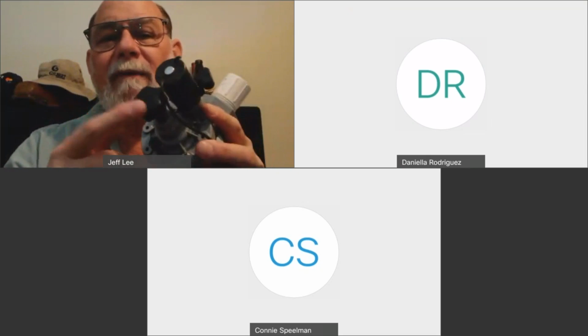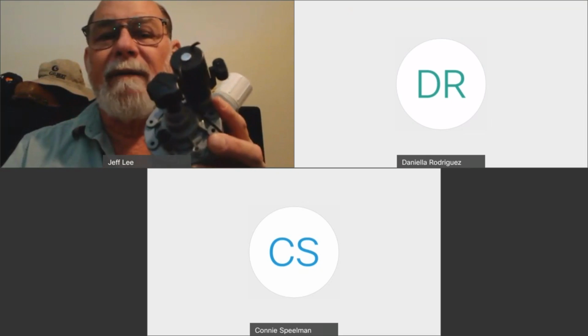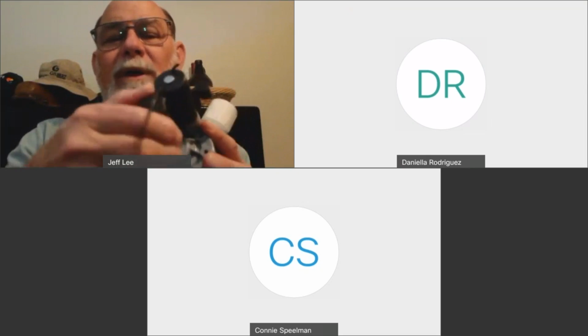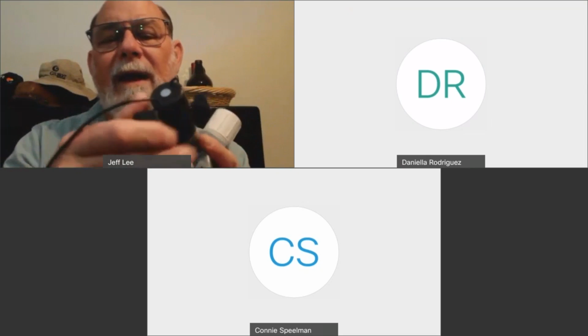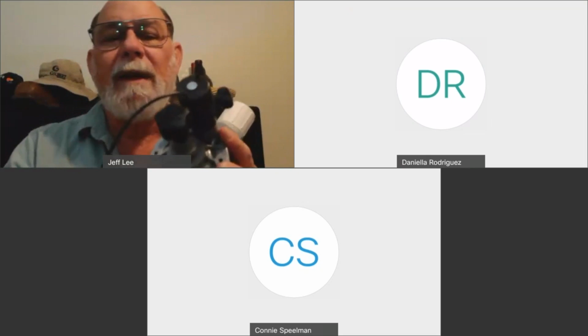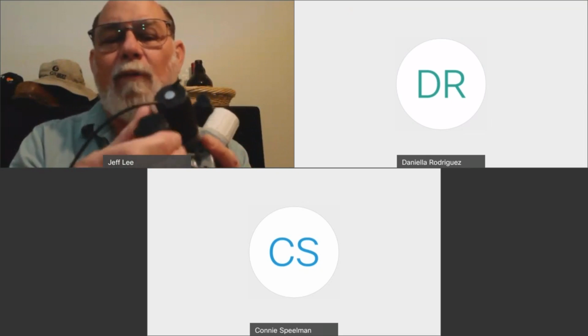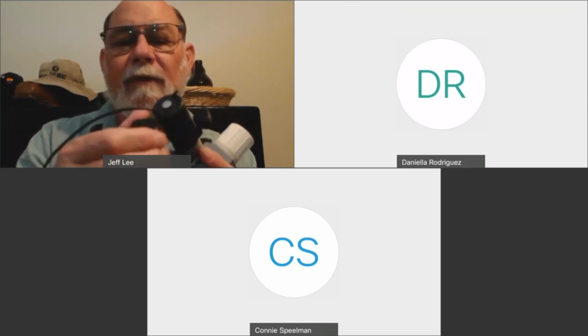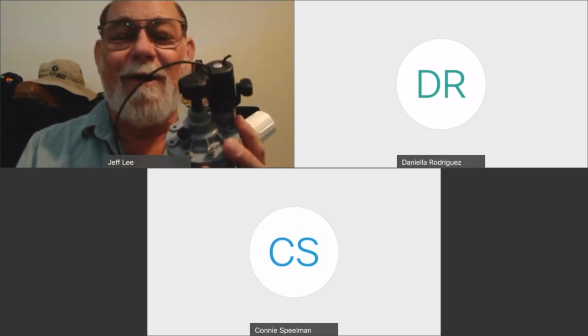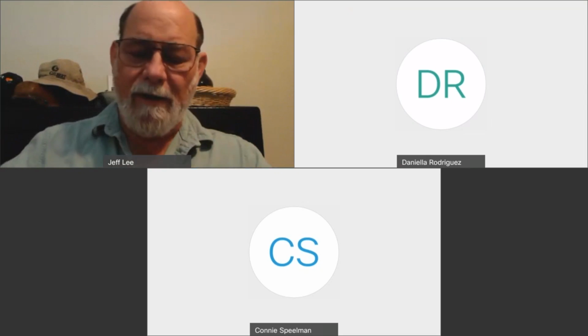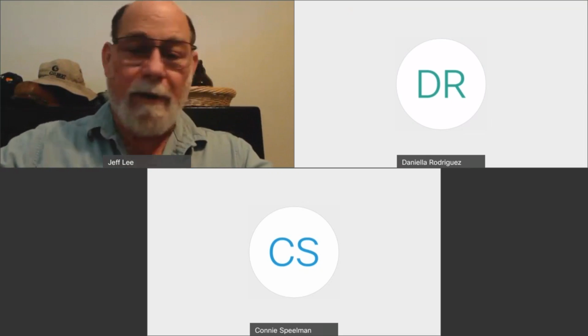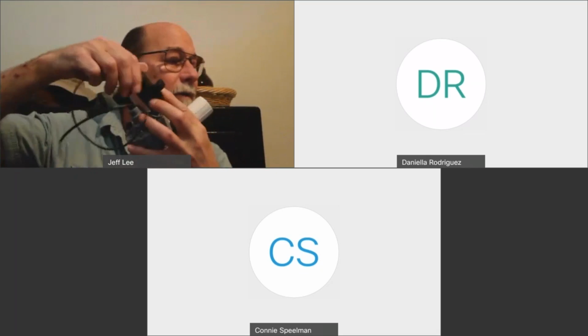Some of your valves may have a larger knob in the middle. We call that a flow control. That will control how far the diaphragm is allowed to open. In most cases, you're going to leave that wide open. So first what you're going to do is you're going to turn off your water supply. And I'm going to go ahead and take off the solenoid here real quick. And it's kind of hard to do here.